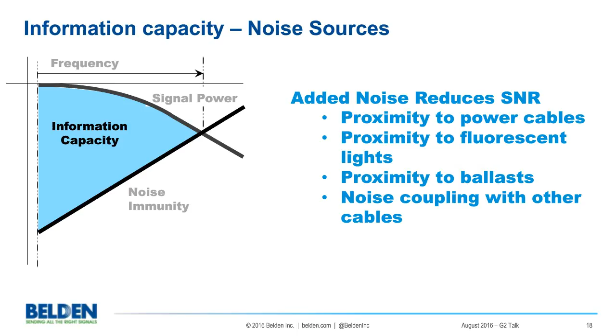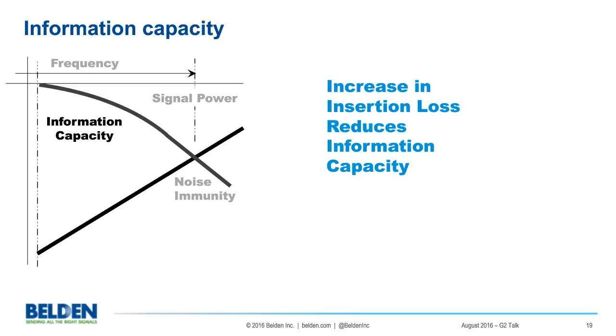Insertion loss, or the upper boundary of this area, can also reduce signal-noise ratio as the cabling becomes more lossy. The areas decrease and the signal-noise ratio is also decreased. This can be attributed to higher temperatures, poor balance. Now you say, how is that? Well, insertion loss is not just attenuation. Insertion loss is attenuation and any other factor that prohibits the signal from going from the point where it's inserted into the cabling to the expected output.